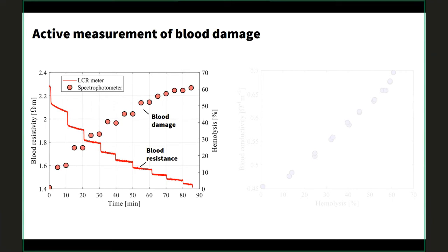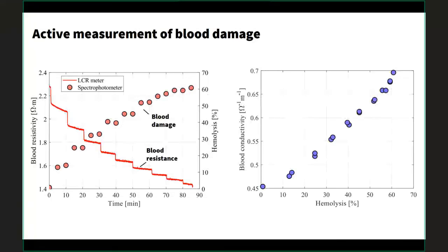We also plotted spectrophotometer readings on the right vertical axis, which give a direct measure of hemolysis percentage — the percent of blood that's damaged. We see the expected inverse correlation: as we added more damaged blood, the hemolysis percentage increased in a step-like manner. Combining these behaviors on the right plot — blood conductivity versus hemolysis — we see the correlation we were looking for: blood conductivity is directly and primarily linearly correlated to hemolysis percentage. We could reliably detect hemolysis down to one or two percent in real time with just a conductivity meter.